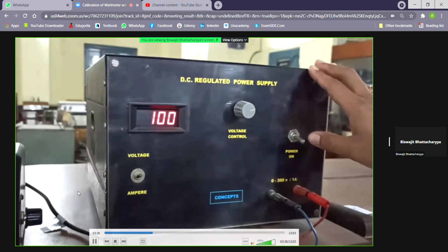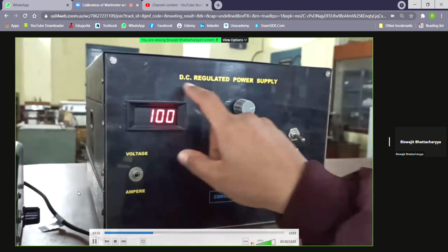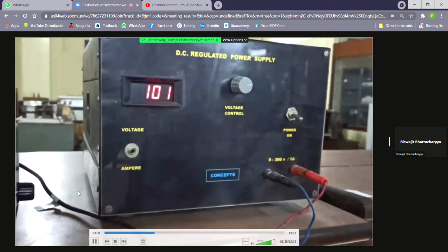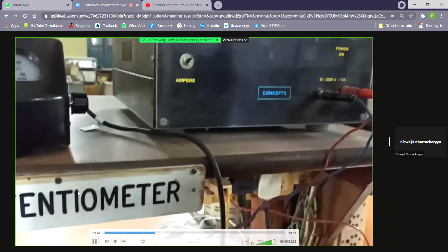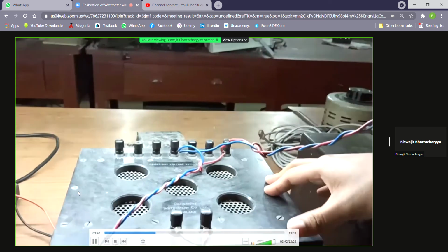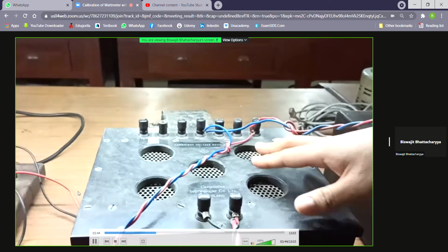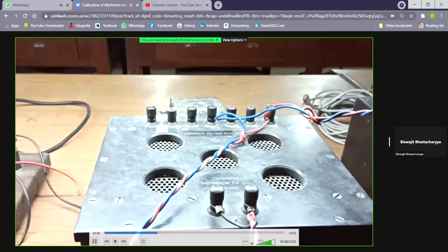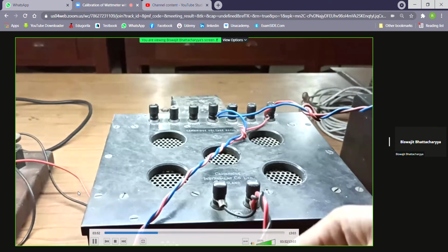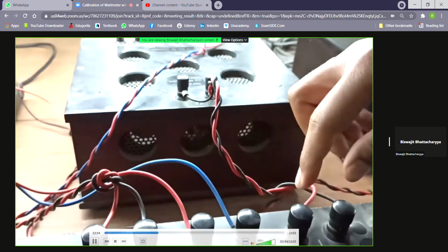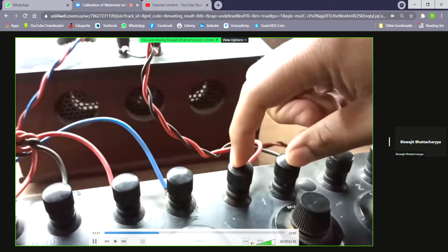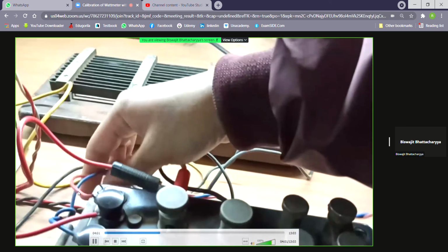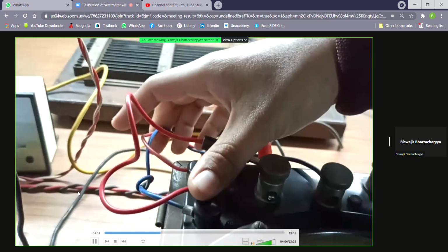This is the voltage supply, and the voltmeter is inbuilt in that. This is the voltage circuit, and this is the volt ratio box, which you are seeing in the circuit. This is 100 volt by 1 volt. This is connected to 1. We are getting 1 volt output for this DC potentiometer in this terminal. And the same line is connected to the potential coil of the wattmeter we are calibrating.